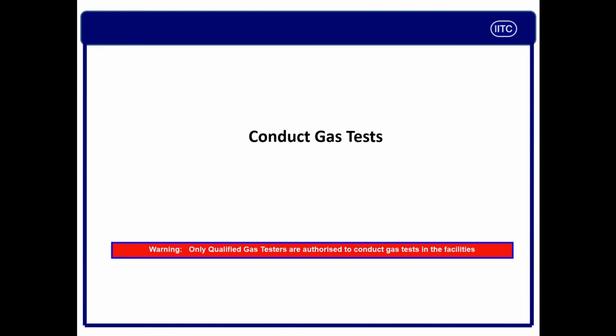Point number 2, ensure the detectors have been calibrated and a certificate of verification is available. Point number 3, ensure that the battery is fully charged. Point number 4, ensure extension and tubing which may be used for testing are clean and in good condition, otherwise you will get a wrong reading.